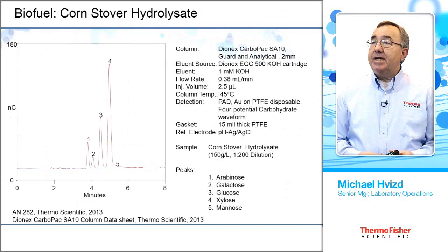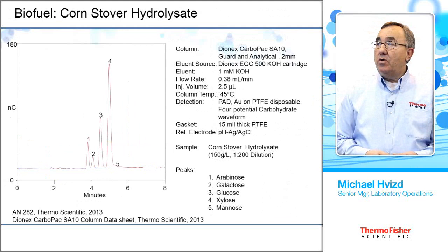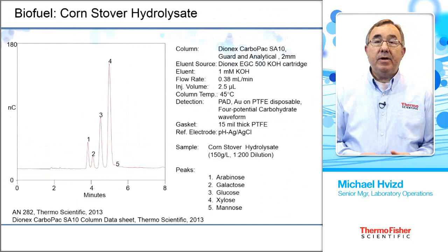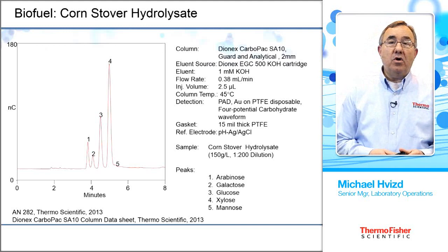An example of a biofuel application: here we're doing corn stover hydrolysate. In this application, we want to make the detector less sensitive, so we use a 15 mil thick gasket, where typically we only use a 1 mil gasket. This thicker gasket slows the linear velocity through the cell, making the detector less sensitive. Because there's an awful lot of sugar here, we don't want to make a very large dilution — we can do a small dilution and inject the sample as is, and that 15 mil gasket allows us to do that.